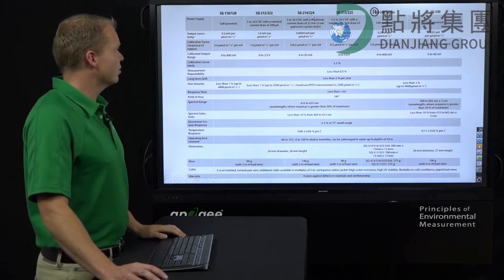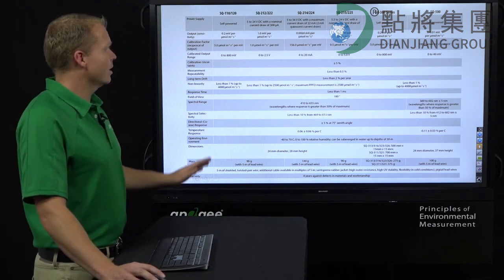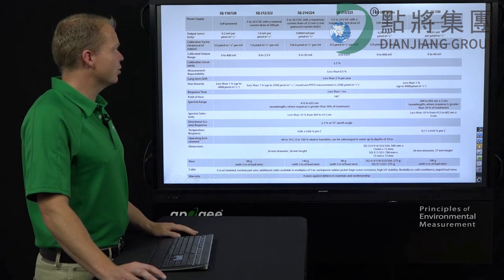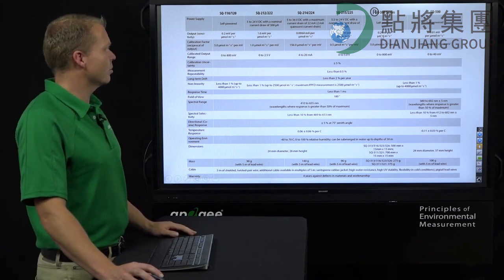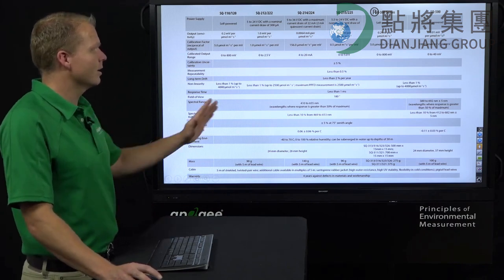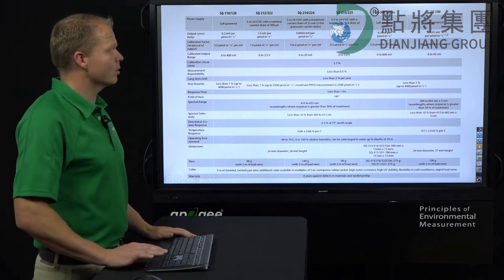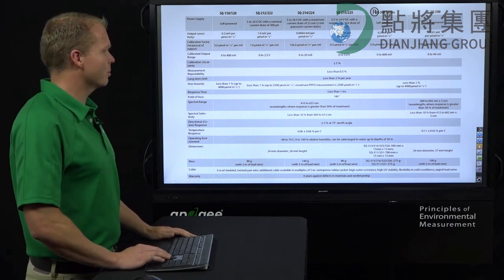For the 214 and 224, you can see this is milliamp per micromole per meter squared per second, and that's 0.0064. And then the 215 and 225 is 2 millivolts per micromole per meter squared per second. The 300 is the same as the 100, where it's 0.2 millivolts per micromole per meter squared per second. And then the 500, that really small signal, 0.01 millivolt per micromole per meter squared per second.